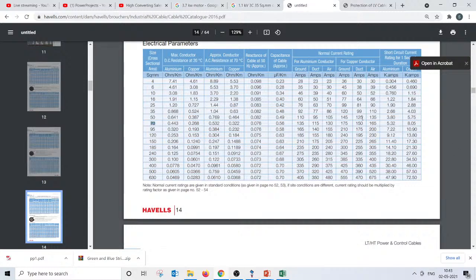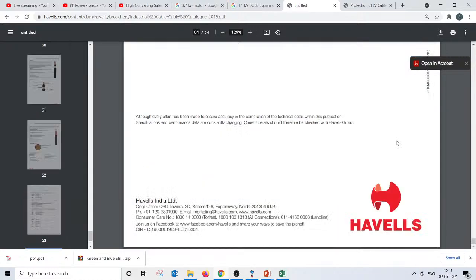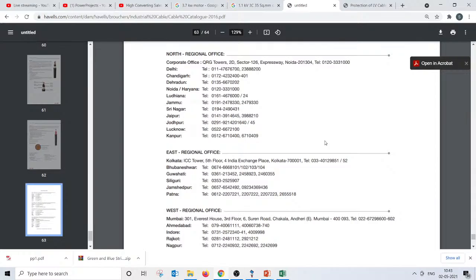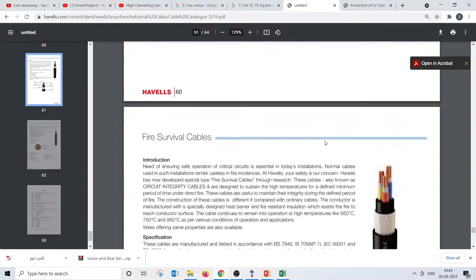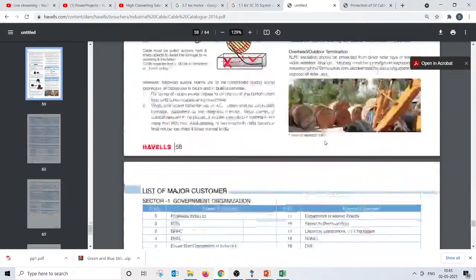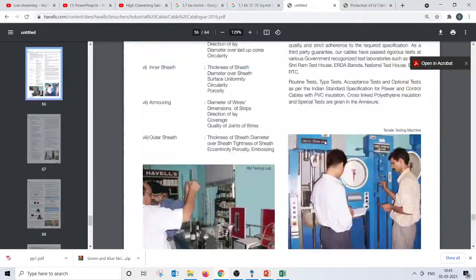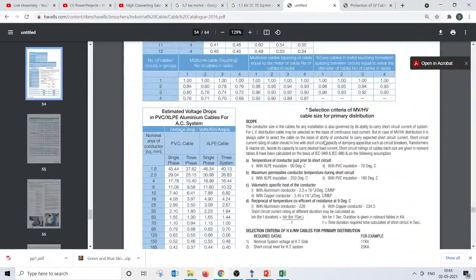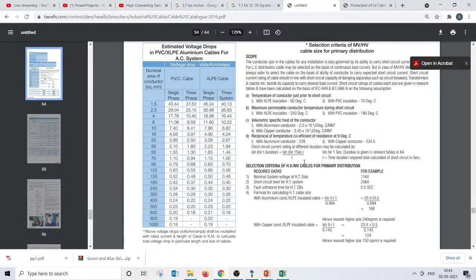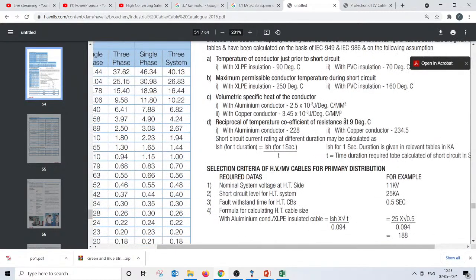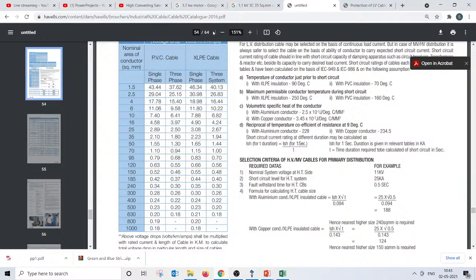I guess there is a formula which you might be using for the short circuit withstand. It is all given in this catalog, like the minimum conductor area which has to be selected, A, an area in square mm, with the formula of this, right? You can refer to the same document which I have shared in the link, and you can see how to size it. The same thing is applicable for HV, medium voltage, and LV.